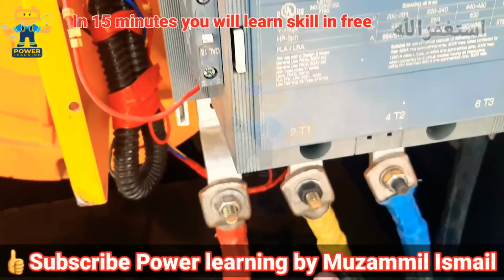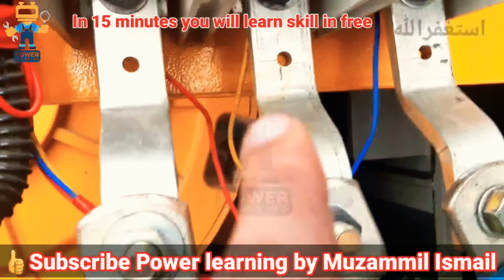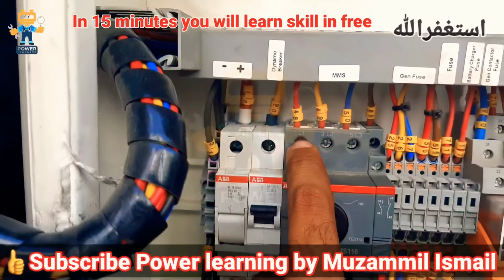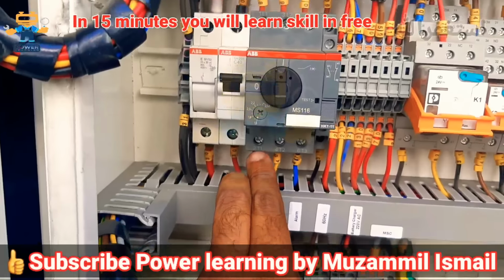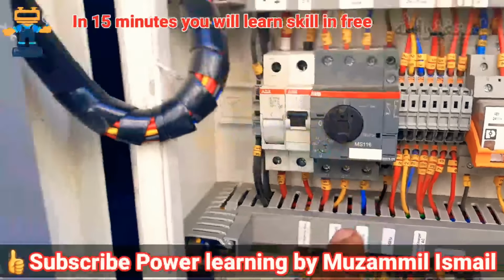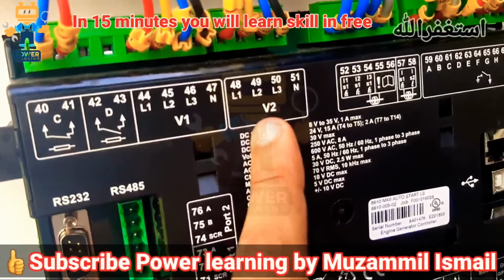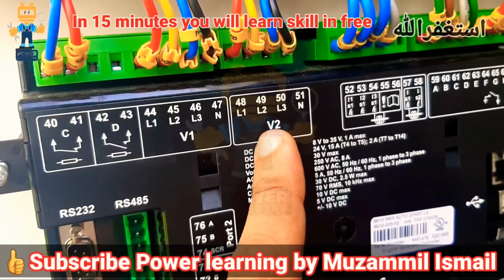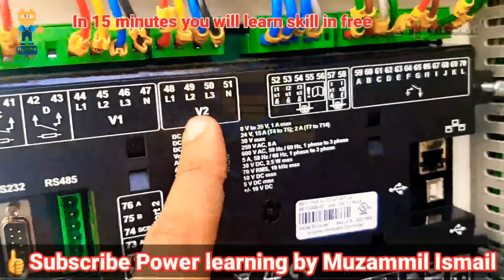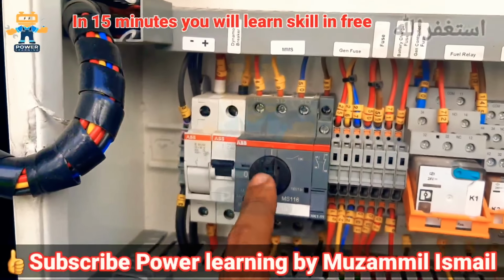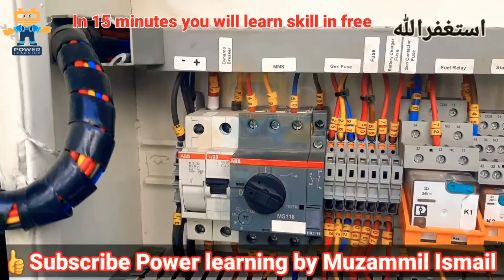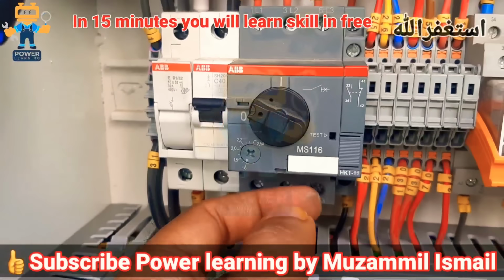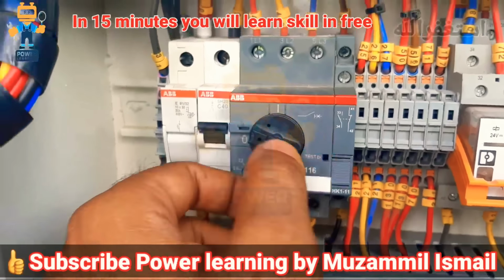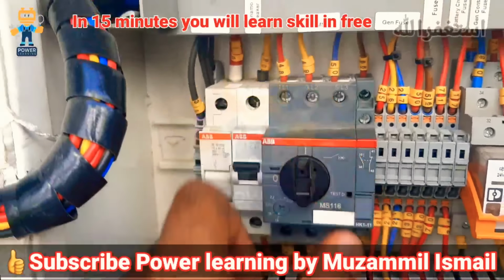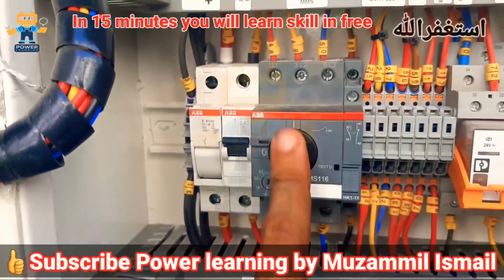We sense 3 phases from here. These 3 control wires are connected here, and after that it is going out from here to V2, sensing the bus voltage. If there is any problem with the bus voltage, this breaker will be tripped like this, in this position. And now I will make it on. So this is here.